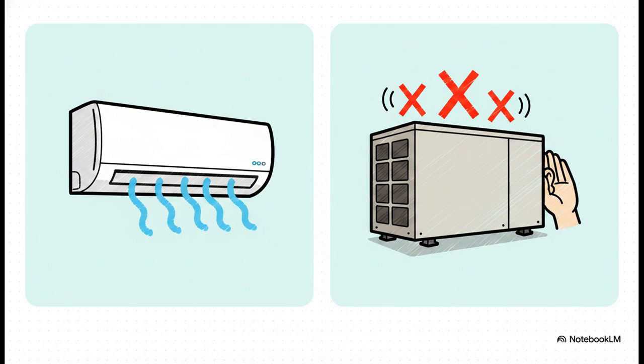This brings us to a critical diagnostic step: you have to clearly distinguish where the error is coming from. Is it the indoor unit, indicated by an internal temperature fault, or an outdoor compressor malfunction? A dead giveaway for the outdoor unit is if your indoor unit runs fine, but outside you don't hear that familiar low hum from the compressor. That tells you exactly where to focus.